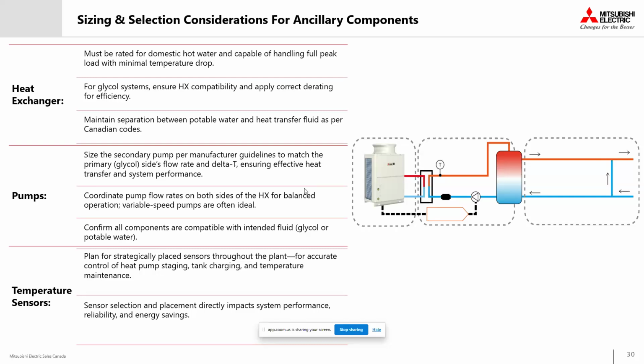Our pumps also need careful selection. The secondary pump should be sized to match the flow rate and the delta T of the primary side for balanced system operation. Because our low recovery, high storage systems generally provide lower flow rates from the internal pumps, it's important to select variable speed secondary pumps that can accurately manage this range. Using a variable speed pump not only ensures balanced performance, but it also helps manage fluctuating demands and improve overall system energy savings.